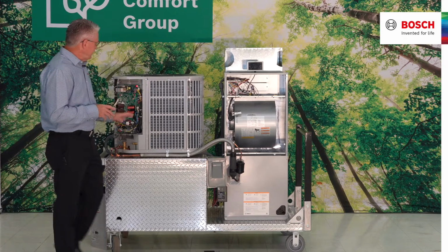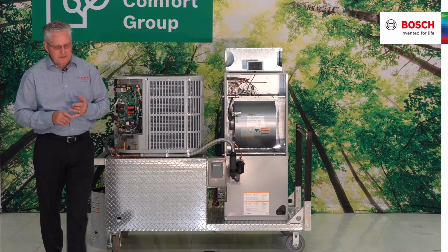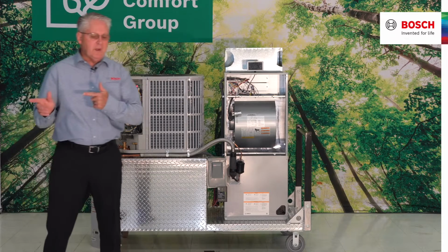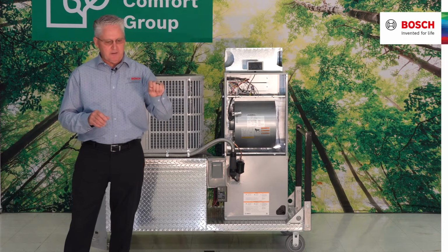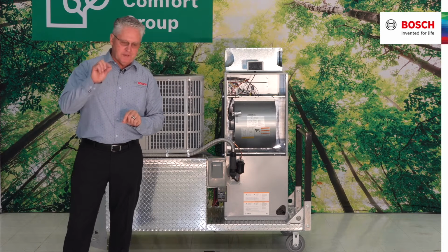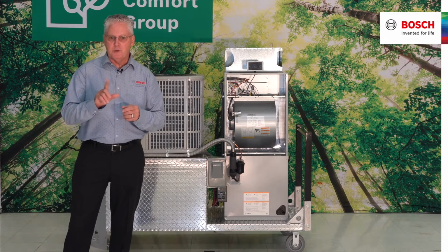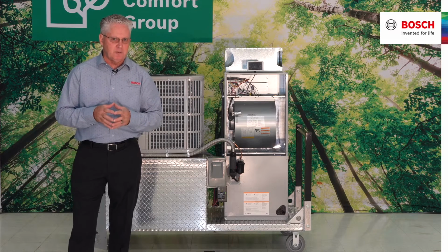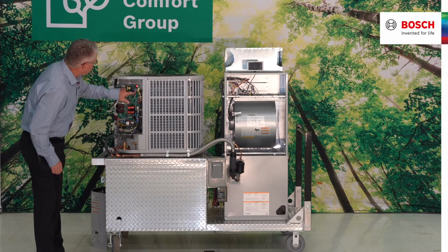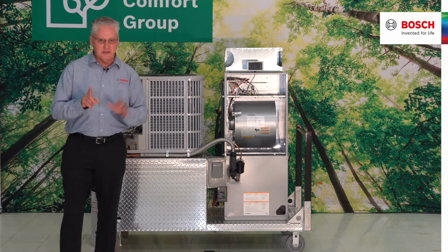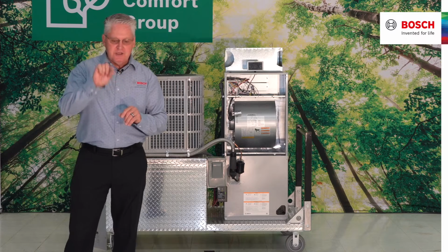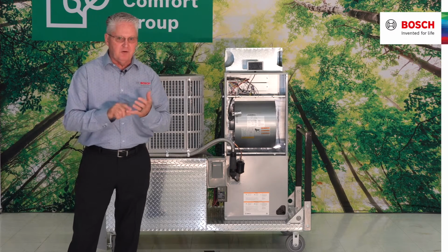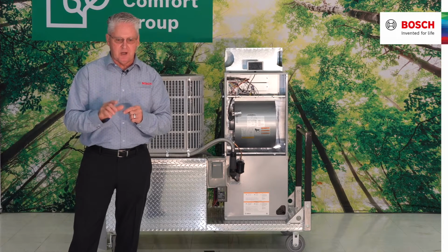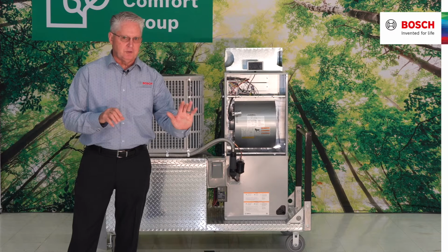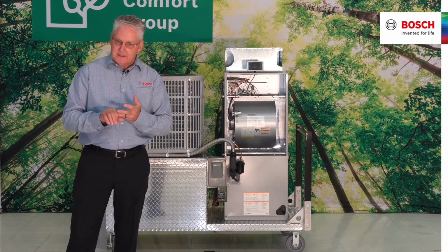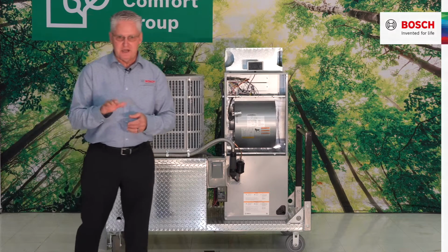So there's a couple changes with the IDS BOVB 15 Seer board. Before, we had the J2 switch that we were able to manipulate, and we could go from a 5-ton to a 4-ton and a 3-ton to a 2-ton and that kind of thing. That J2 switch logic is still there, but it's not called J2 anymore. This is located right there, and it is actually SW6, okay, SW6. And where you have those dip switches located on this particular BOV 036 is where it's going to get its logic. Is it a 3-ton capacity or is it a 2-ton capacity? So remember, SW6 on the 15 Seer, and it's not a J2 anymore.